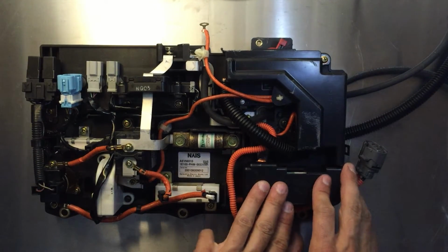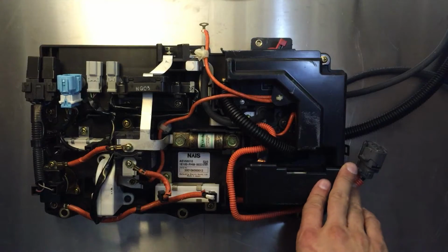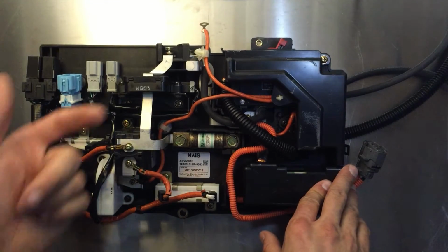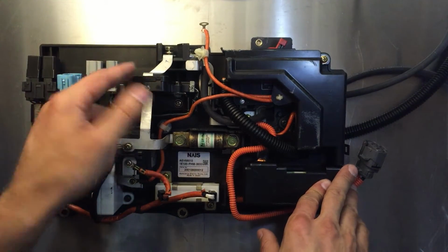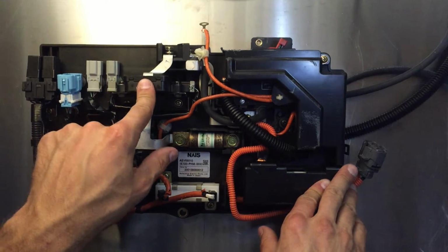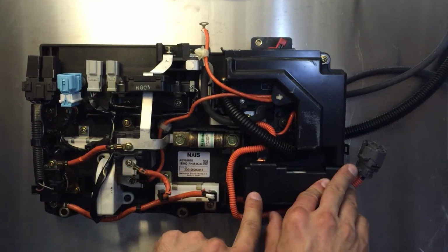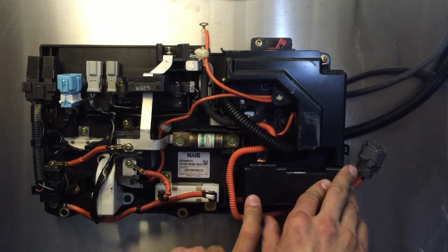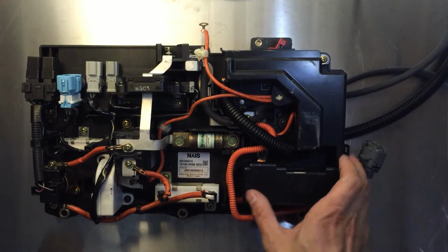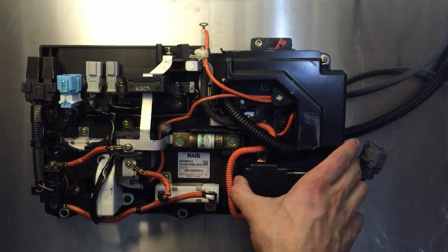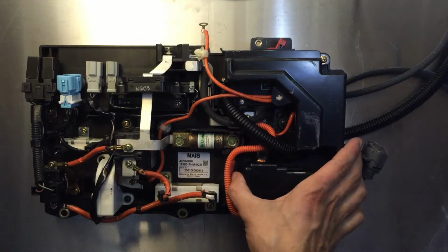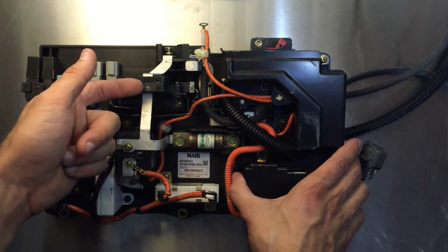It knows the DC-DC is consuming 5 amps. We ultimately don't really care how much the motor delivery unit is consuming, because the DC-DC current is going to be relatively low. At 50 amps on the DC output, it's only 5 amps on the input, so I couldn't really care less if I'm pulling 105 or 110 amps here.